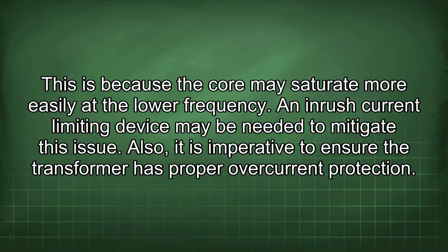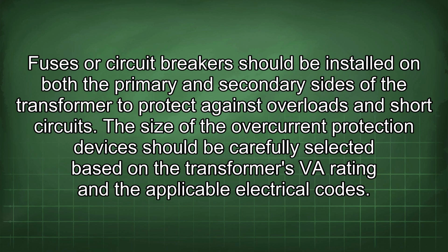Also, it is imperative to ensure the transformer has proper overcurrent protection. Fuses or circuit breakers should be installed on both the primary and secondary sides of the transformer to protect against overloads and short circuits. The size of the overcurrent protection devices should be carefully selected based on the transformer's VA rating and the applicable electrical codes.